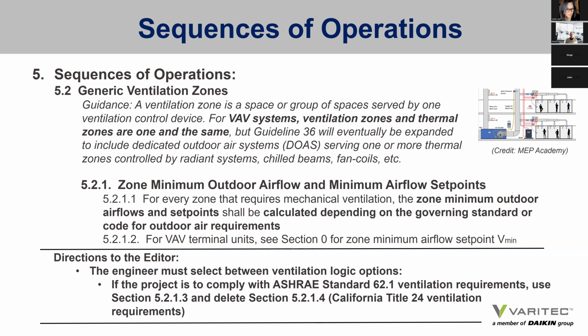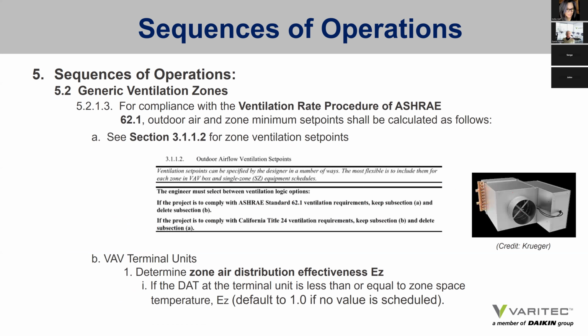And then there's direction provided that identifies that an engineer needs to decide whether they're designing to the standard 62.1, or if they're in California, they're going to be using California Title 24, and they have to use the appropriate language to meet either of those codes or those standards. So there are generic ventilation zones, and for compliance with the ventilation rate procedure of ASHRAE 62.1, this Section 5 is very clear on adopting 62.1's calculations for assigning the appropriate zone ventilation rate.